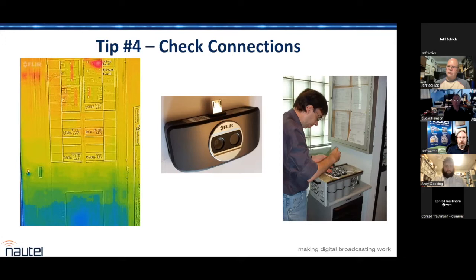So if you're running 6-gauge stranded into lugs for the AC connection on a new transmitter, you tighten them down, then you come back next week, you tighten them down again, you come back next month, tighten them down again, come back a couple of months later, tighten them down again. At that point, you can probably say they're okay. The same goes if you're running a 2-gauge copper wire, that quarter-inch copper cable out to a ground lug on a ground rod - not a fan. So definitely check those.